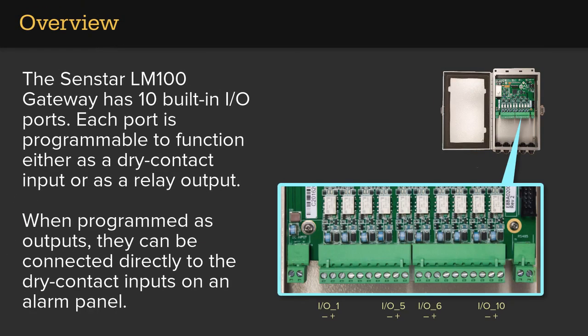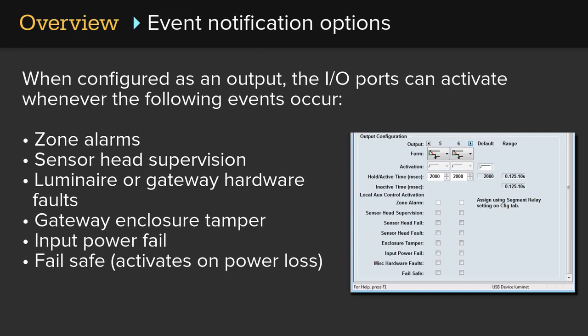The Senstar LM100 gateway has 10 built-in I/O ports. Each port is programmable to function either as a dry contact input or as a relay output. When programmed as outputs, they can be connected directly to the dry contact inputs on an alarm panel.